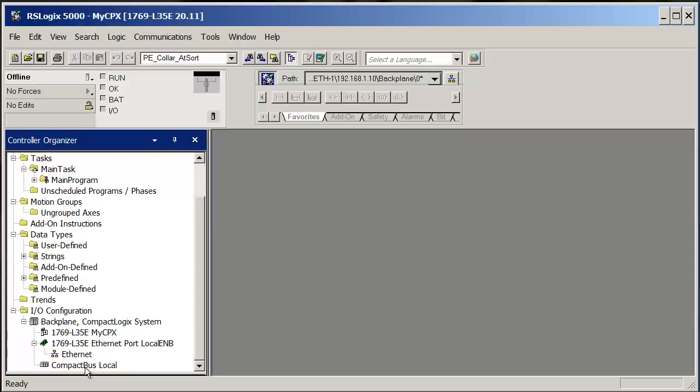They don't really call it a backplane, they call it a bus. An I/O chassis has a backplane, which is the circuit board that goes the full length of the back of the chassis that has connectors on it, and when you slide I/O modules into the chassis, they slide into the connectors that are on the backplane.